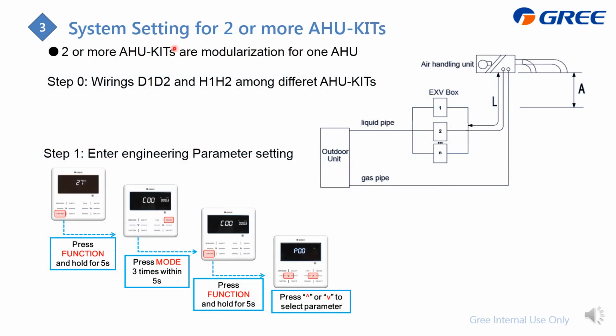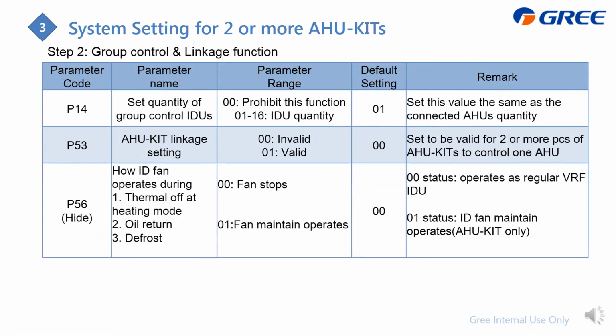Next is the summary of the system setting for 2 or more AHU kits. When you install the system like this, with modularization of the AHU kits to control the AHU, it requires D1, D2, and H1, H2 among the different AHU kits. After that, on the wired controller, which is this one, you need to follow this password to enter the engineering parameter setting, which is to change the P codes, including P14 to select the group control, and make this your actual connected AHU quantity. P53 is for the AHU linkage setting. We need to link these modularized AHUs to make them control the same, just like a group.